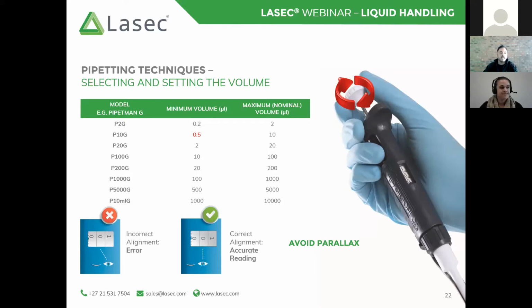Okay, so like I said right at the beginning, pipetting is a system. So if the tip is of poor quality, if the tip does not fit the pipette, or if the tip is not suited for that application, that system is not going to work accurately or precisely. And that is exactly what we want to achieve by using a pipette: accuracy, precision and reproducibility for other results. Okay. So we are now going to touch on pipetting techniques, starting from the beginning, and what to do with the pipette.